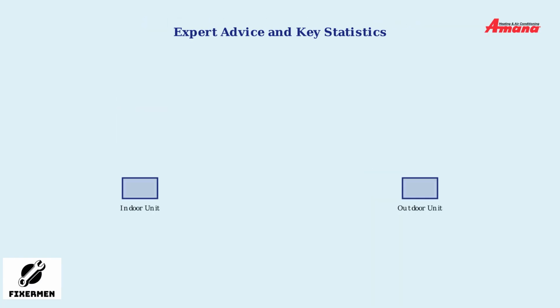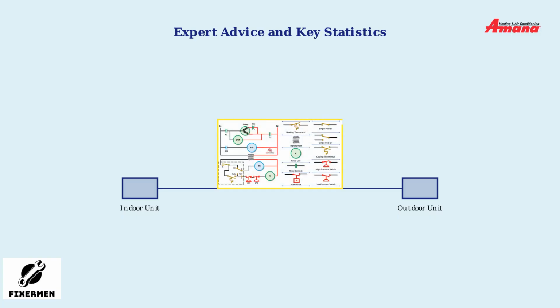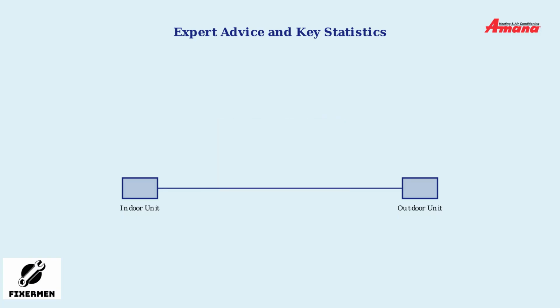HVAC experts strongly recommend thoroughly checking wiring connections before considering part replacements. Wiring faults are responsible for the majority of F07 communication errors in Amana systems. According to industry data, wiring issues cause approximately 65% of all F07 error codes. This includes loose connections, damaged wires, or voltage drops that interrupt the communication between indoor and outdoor units.